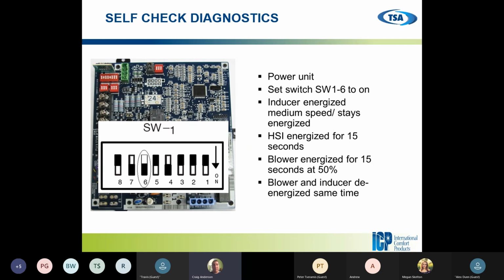So when we power up the unit and we set our SW1-6, what's going to happen is our inducer is going to energize at medium speed. It's going to stay energized. Our HSI is going to come on for about 15 seconds. Then it's going to turn off. Our blower is going to energize for 15 seconds at about 50%. Blower and inducer are going to de-energize at the same time. So we're testing the blower, the inducer, and the hot surface igniter. The gas valve is not going to energize at any time. We're not testing the gas valve. We're checking our safeties and making sure what's going on in our furnace with this test sequence.